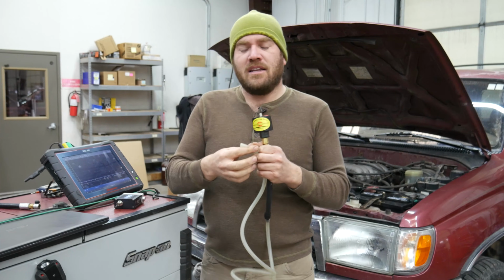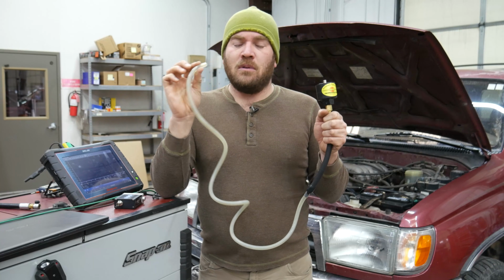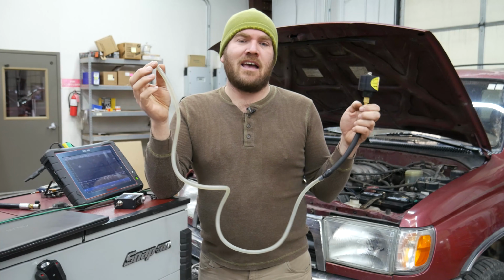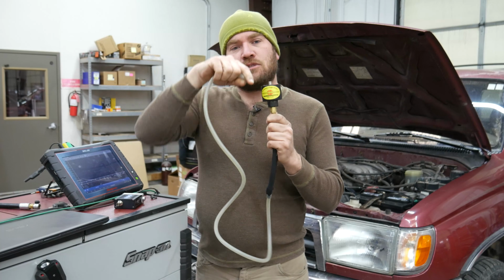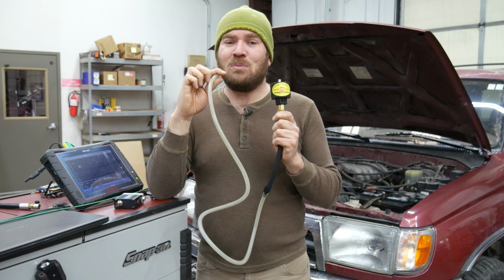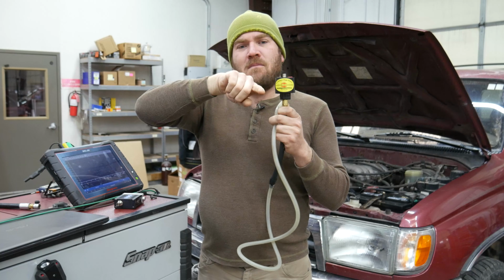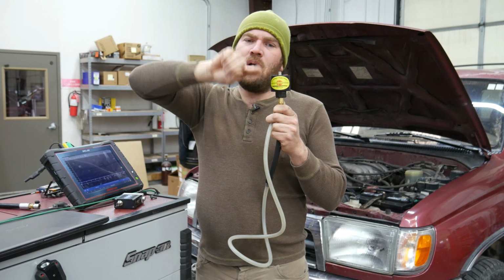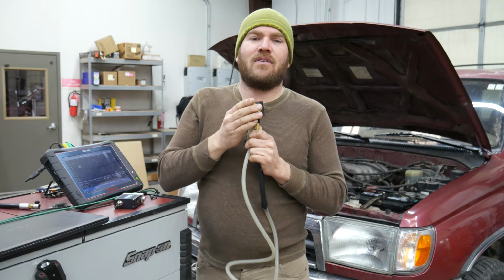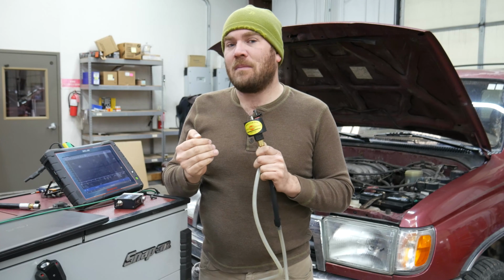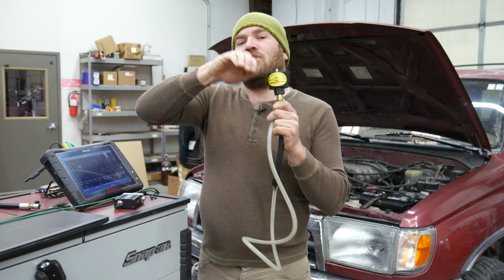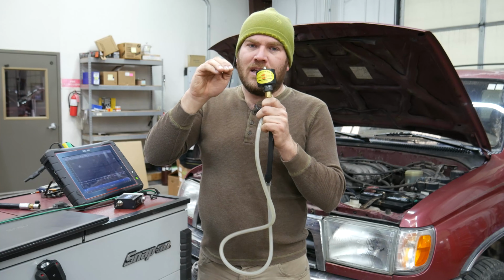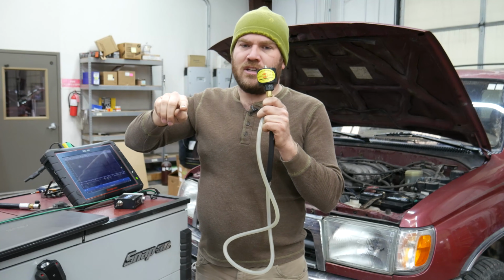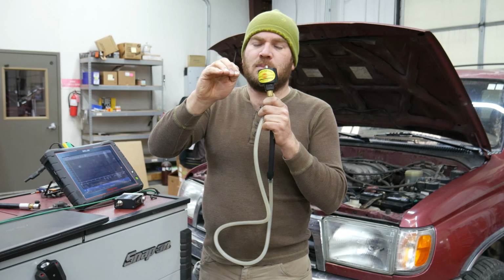The other thing to keep in mind is if I were to blow in this and apply, say, 1 psi of pressure, I'm going to see a spike in my waveform. And even if I keep blowing and holding that pressure in there, my spike isn't going to go up and stay there. It's going to go up and then drop down because as soon as that diaphragm quits moving, it stops generating power. So it's going to deflect up, generate some power, and then the voltage is going to drop back to zero, even though that diaphragm is held up.